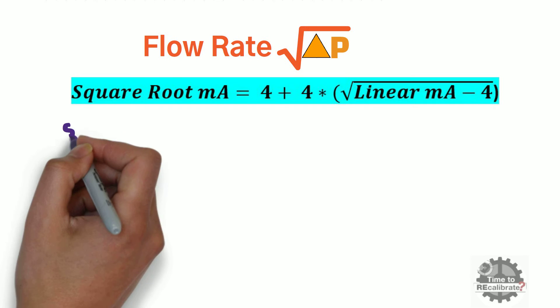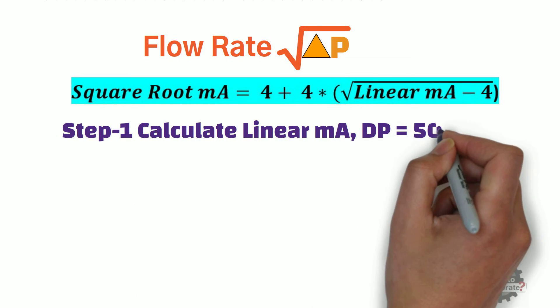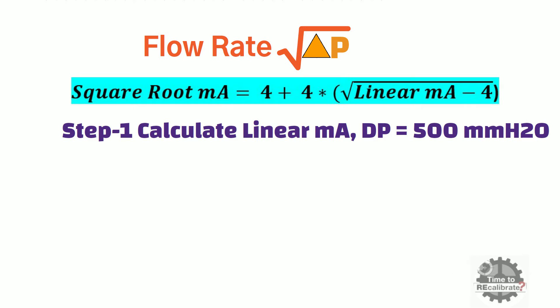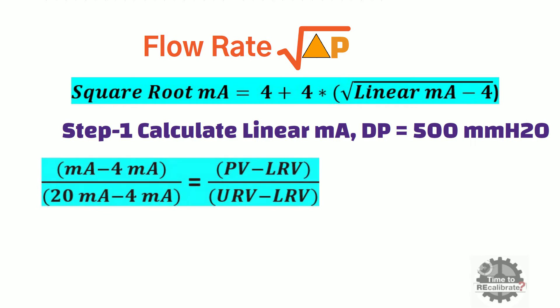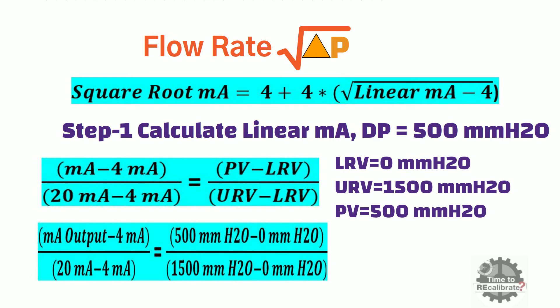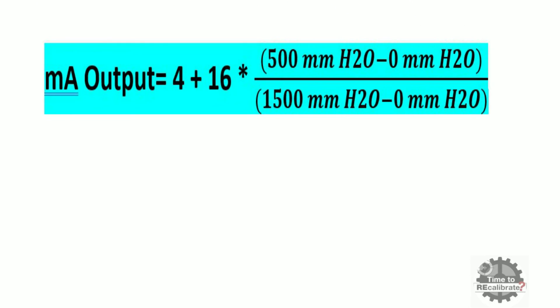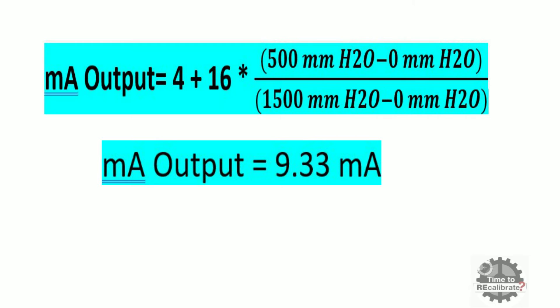So in step number one, I am going to find the value of linear milliampere when differential pressure is 500 mm H2O. This is the standard equation to calculate milliampere value. Now put the values of lower range value, upper range value, and process variable value in this equation and do the simple math calculation. When you do the math calculation, you will get 9.33 milliampere, which is our linear milliampere value.